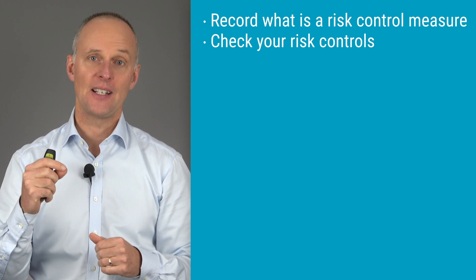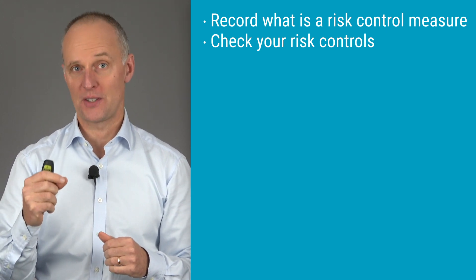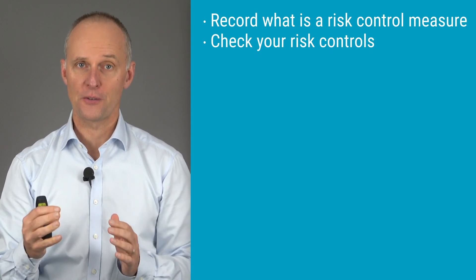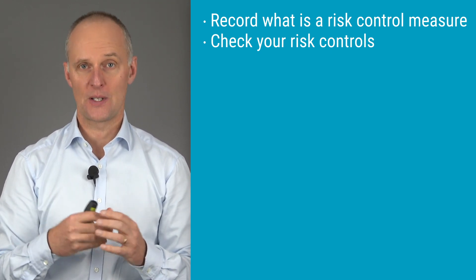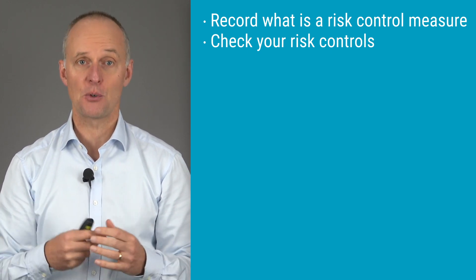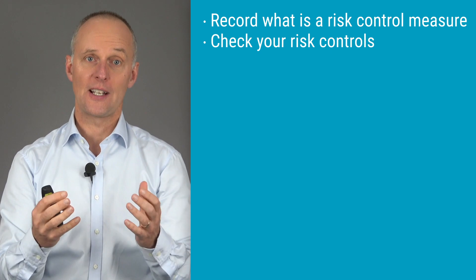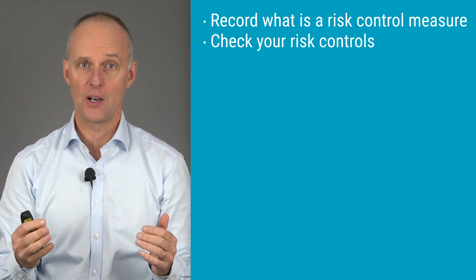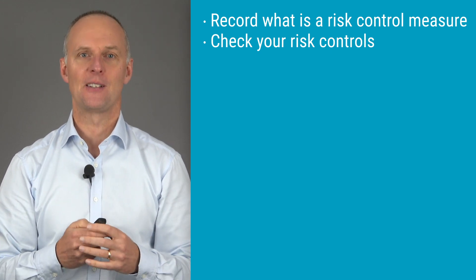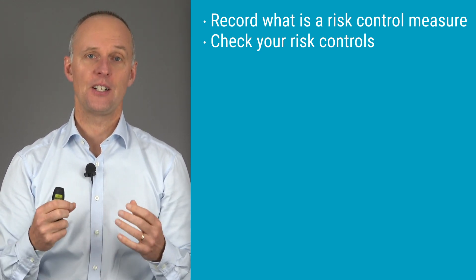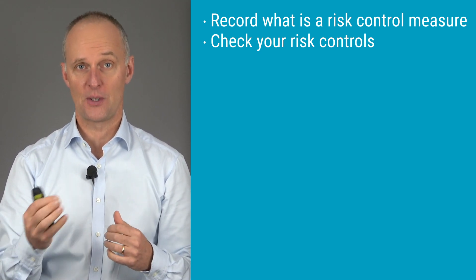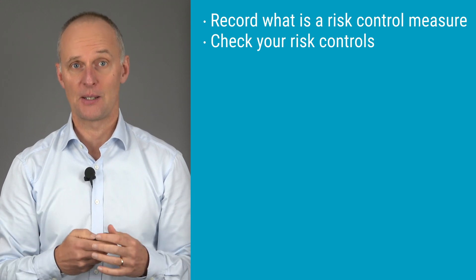Another argument is that it may be wise to show how much your risk control measures actually lower the risk. Comparing the risk before and after risk control helps you check the effect of your risk control, which in turn can help you find mistakes and incorrect assumptions. For example, if a warning in the instructions reduces the risk more than a safeguard or protective measure, then you might suspect that a mistake has been made. You can easily do this check by multiplying PO with S in your hazard traceability matrix before and after risk controls to compare the resulting products.